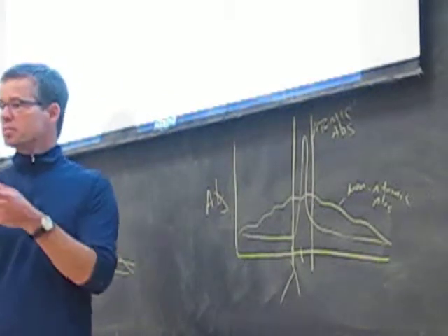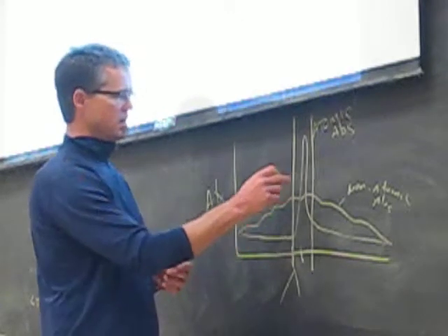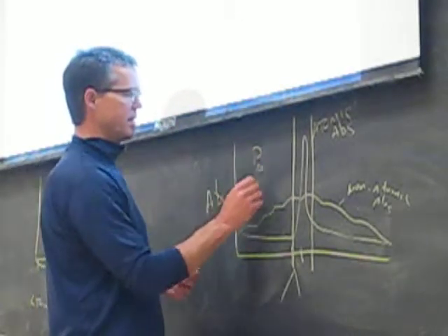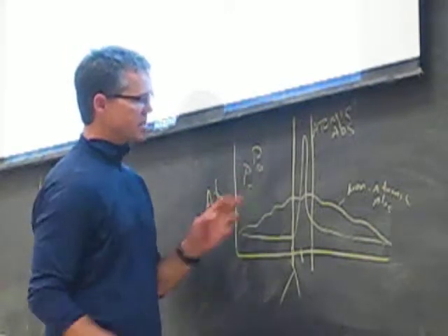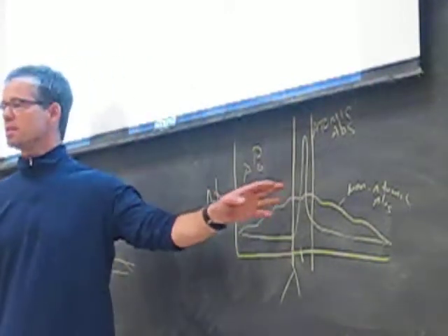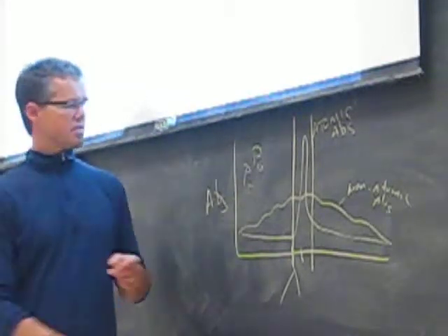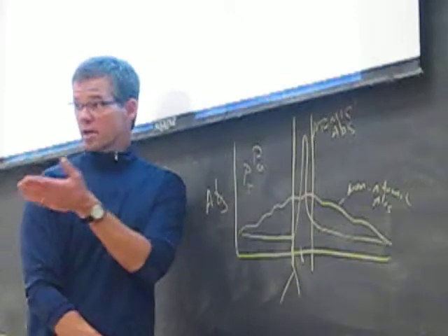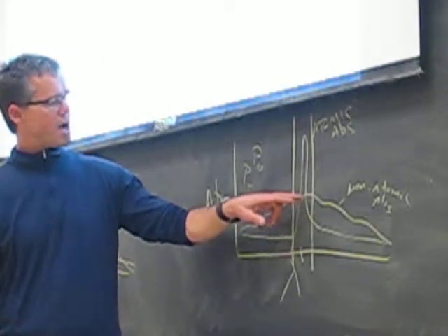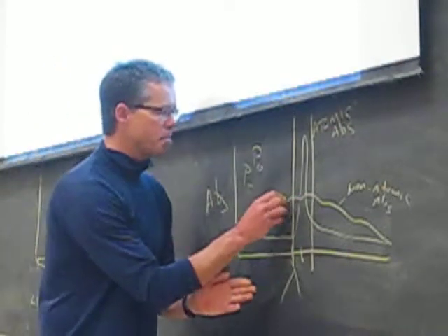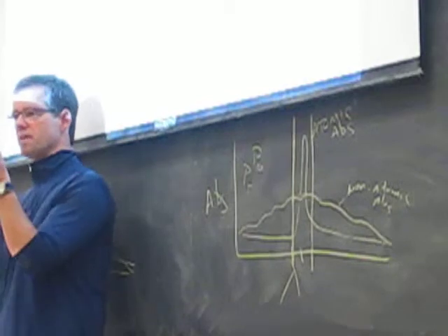Right? And in your instrument, you are in real time measuring how much of the absorbance, when I'm looking at the light that's coming out, the incident light, and the light that's actually striking the detector, I'm comparing those two to measure the actual absorbance, just the same way. How is it, in this case, that you might be able to correct for non-atomic absorbance that happens to pass that same band of wavelengths, or that same wavelength band?